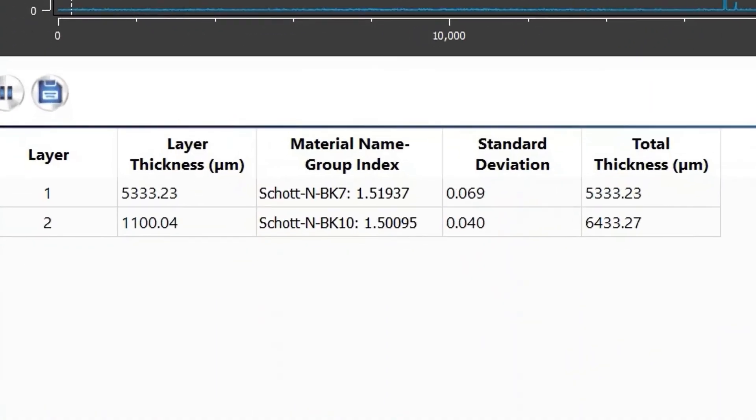Now the OptiCal software is displaying the thickness of each element measured in microns, the material name, the group index, the standard deviation of measurement, and the total thickness in microns.